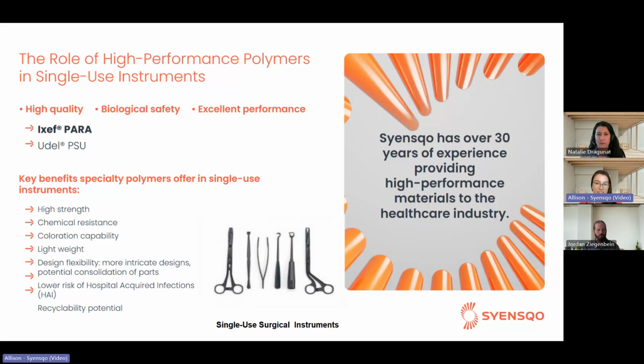Single use might be a slight misnomer, as these instruments are used multiple times, but just on one patient. So just for one surgery. These devices are not designed for repeat sterilization, but the benefit is that there is more design freedom available because there's a decrease in the amount of extreme conditions these parts will see. In general, Ixef, which you'll see bolded, is our main go-to for single-use instrumentation. But UDEL PSU is a unique offering that can provide a little bit more ductility and toughness versus XF. But for a standard metal to plastic transition, we would normally consider our Ixef PARA here.